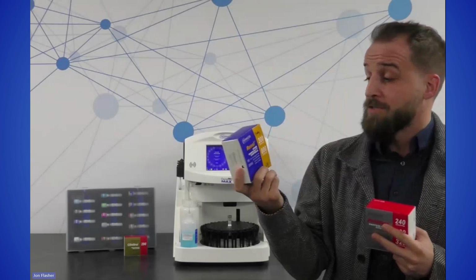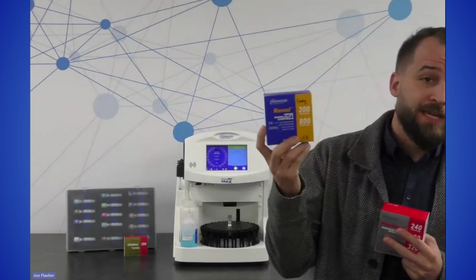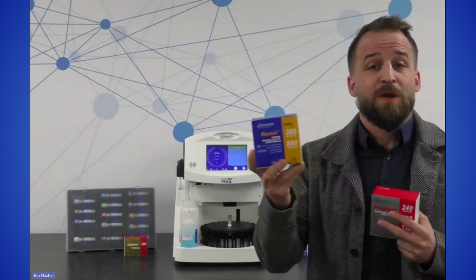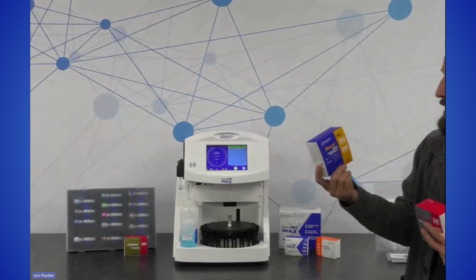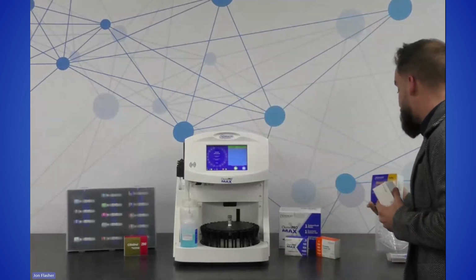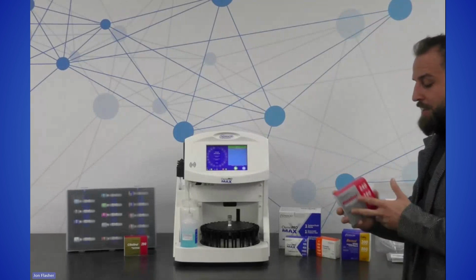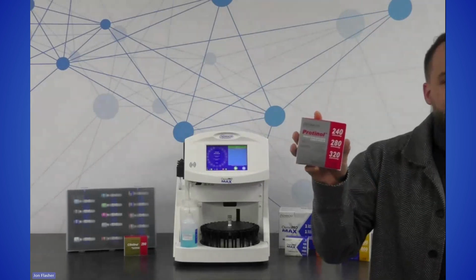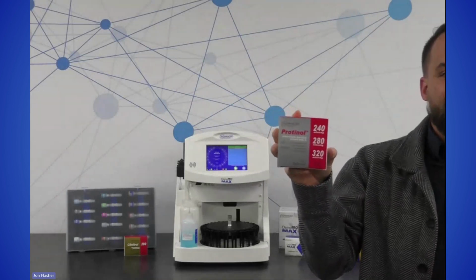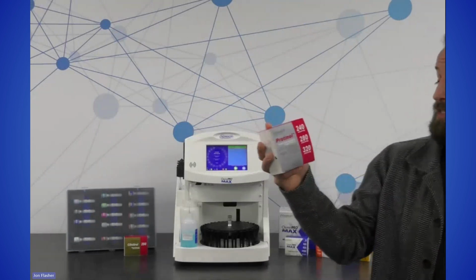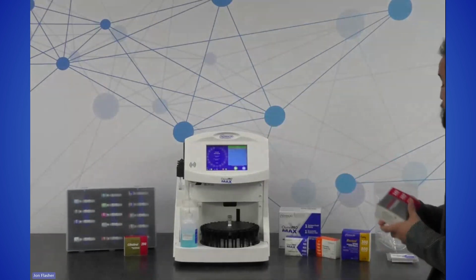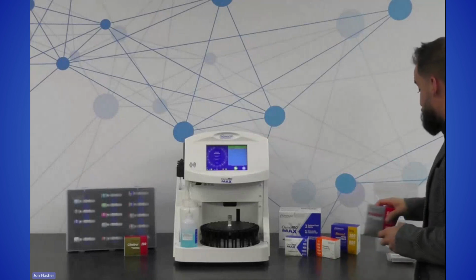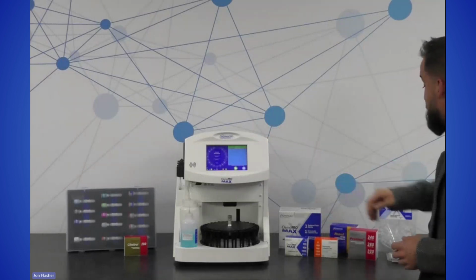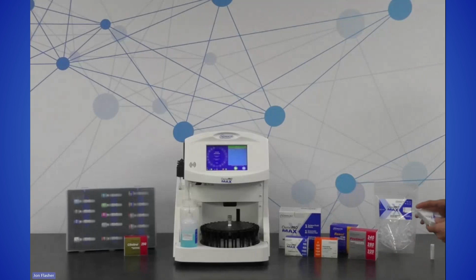So it also takes into account the range of results that you would expect under normal circumstances from a urine sample, so 300 and 800 milliosmol standards. And then for our Protinol, similar concept, it really captures the range that you might expect in normal circumstances from serum and plasma, so 240, 280, and 320. So that's what we offer from a control, linearity, calibration, and maintenance perspective.